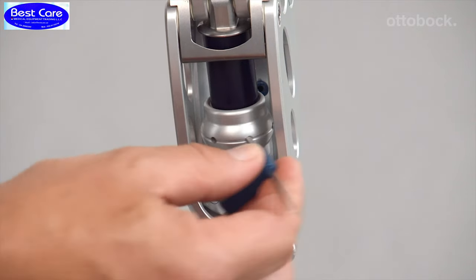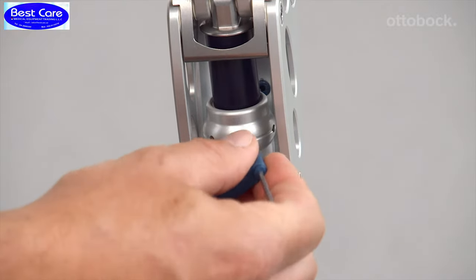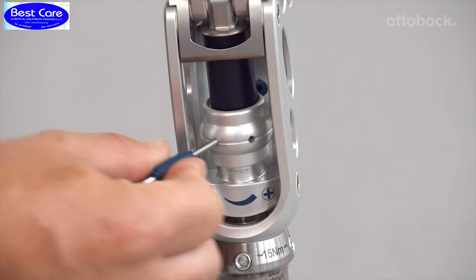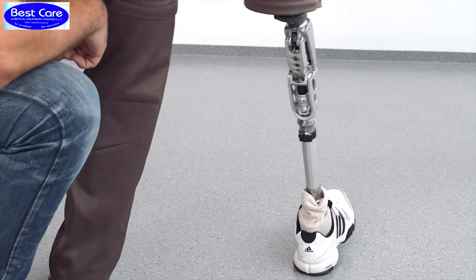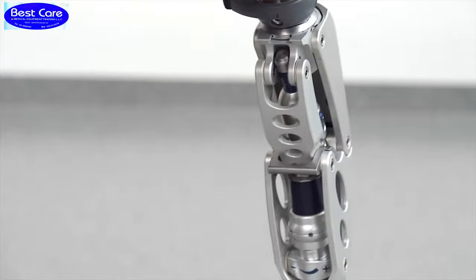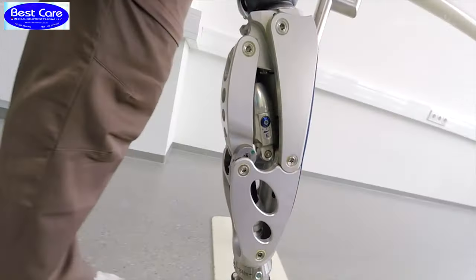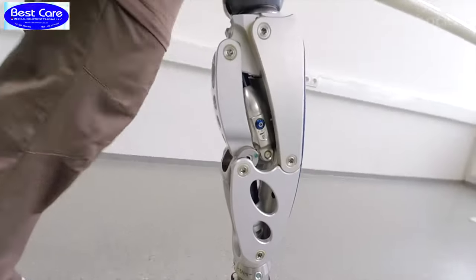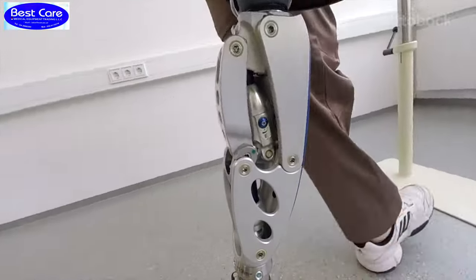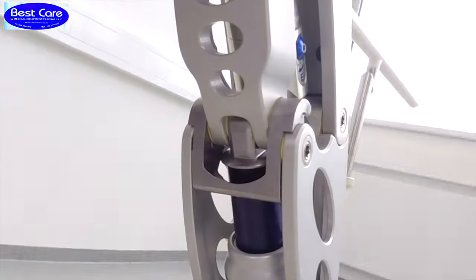The resistance of the EBS unit is decreased. More knee flexion is possible and the pivoting mount raises faster. The round spring of the EBS unit must be adjusted so that the pivoting mount does not permanently stay in the end position. Please compress the EBS unit a bit more so that the user experiences increased comfort at heel strike and targeted control of the stance flexion.